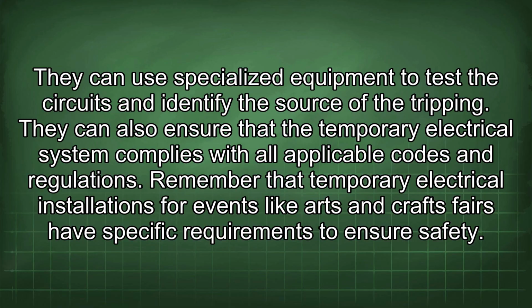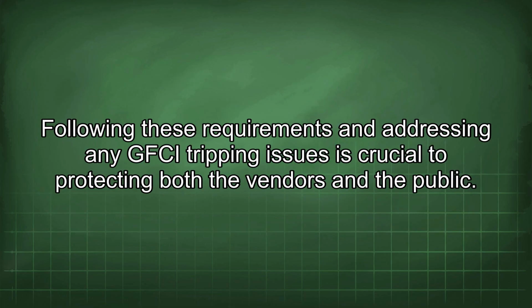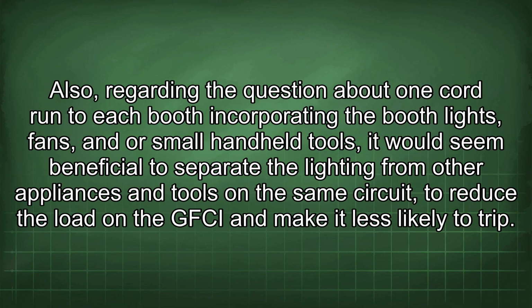Remember that temporary electrical installations for events like arts and crafts fairs have specific requirements to ensure safety. Following these requirements and addressing any GFCI tripping issues is crucial to protecting both the vendors and the public. Also, regarding the question about one cord run to each booth incorporating the booth lights, fans, and/or small handheld tools, it would seem beneficial to separate the lighting from other appliances and tools on the same circuit to reduce the load on the GFCI and make it less likely to trip.